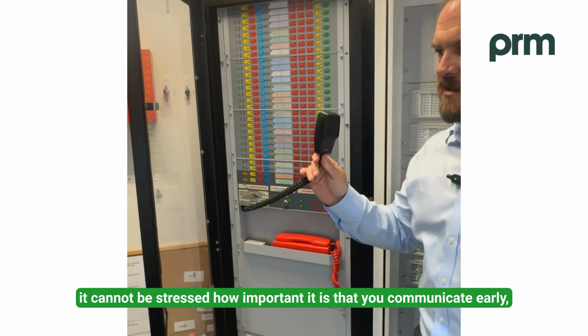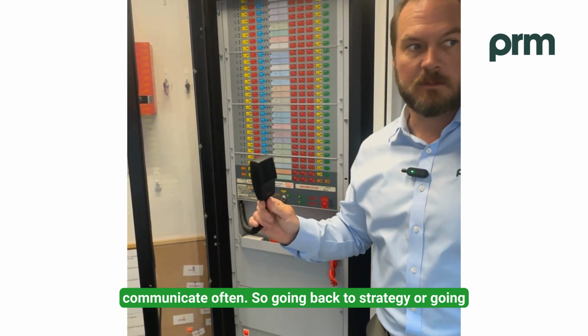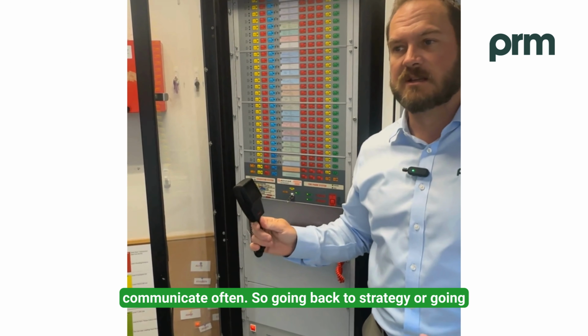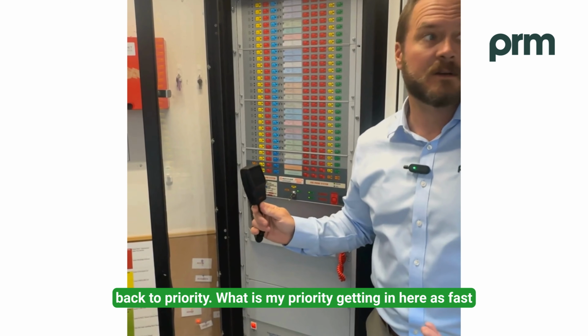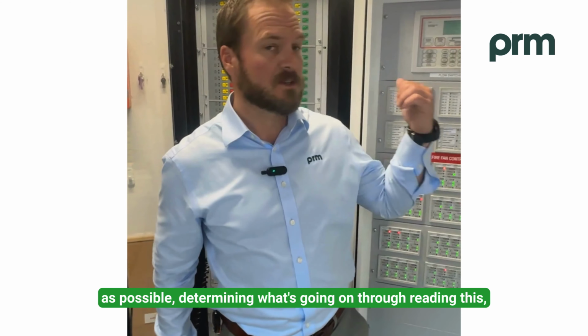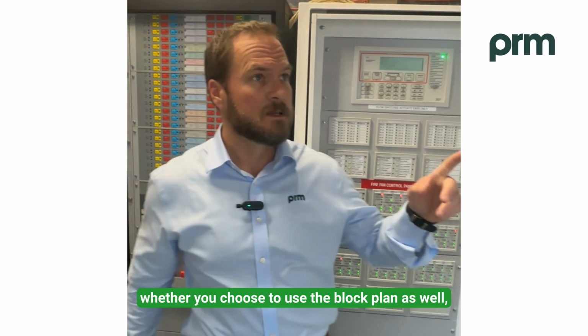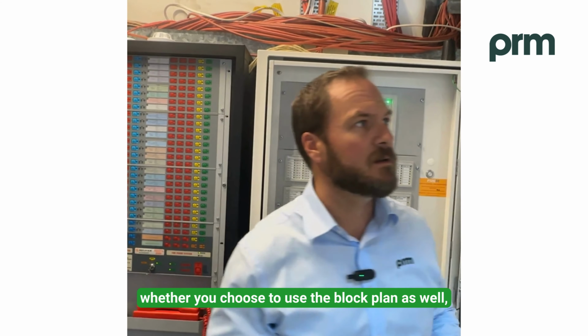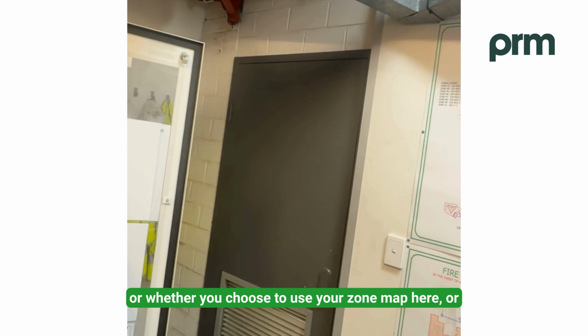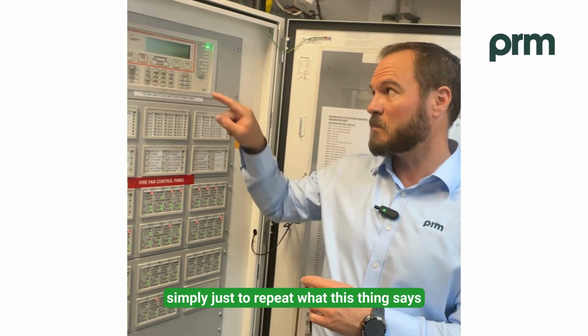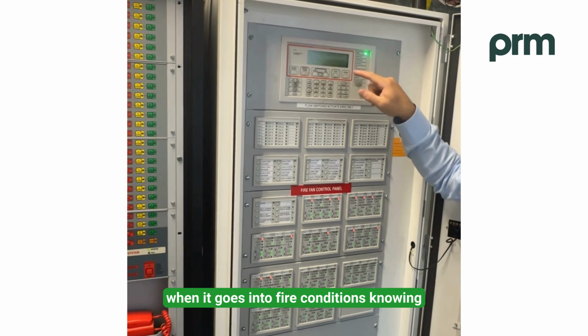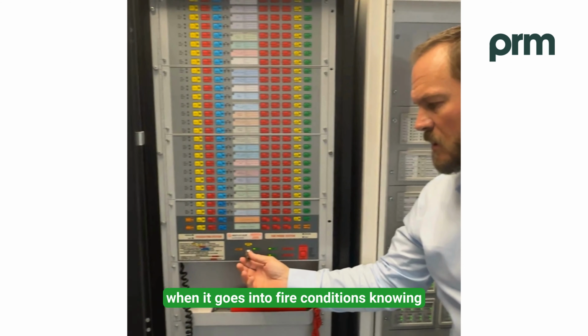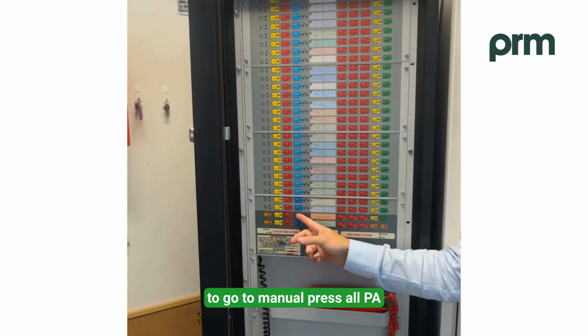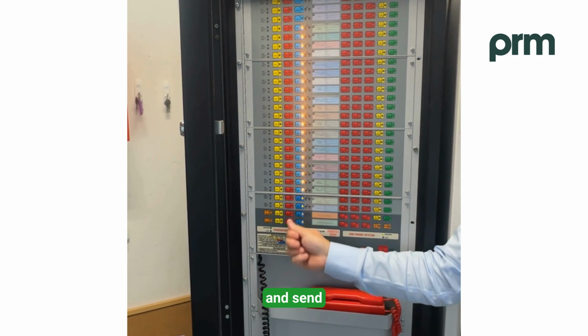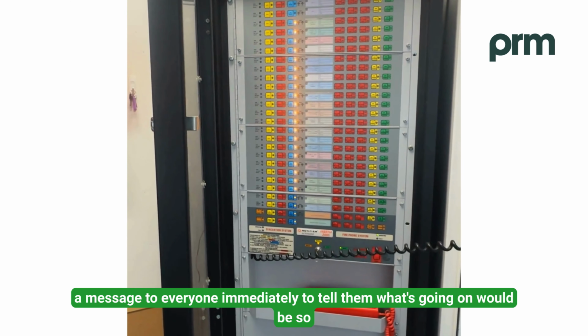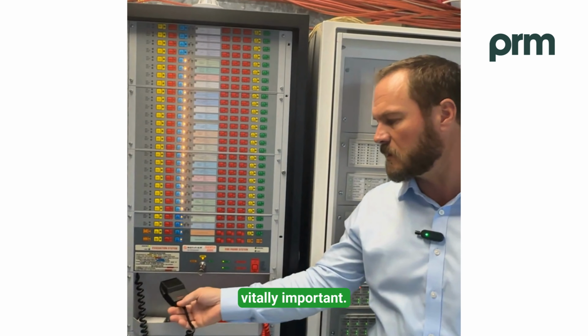And it cannot be stressed how important it is that you communicate early, communicate often. So going back to priority, what is my priority? Getting in here as fast as possible, determining what's going on through reading this, whether you choose to use the block plan as well, or whether you choose to use your zone map here, or simply just to repeat what this thing says when it goes into fire conditions. Knowing to go to manual, press all PA, and send a message to everyone immediately to tell them what's going on would be so vitally important.